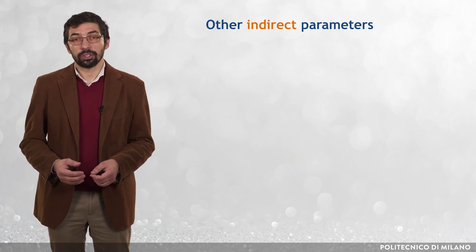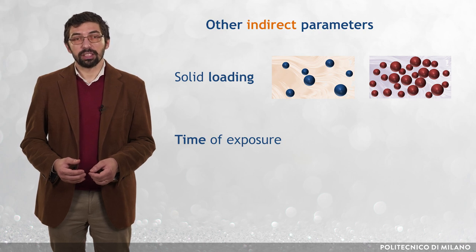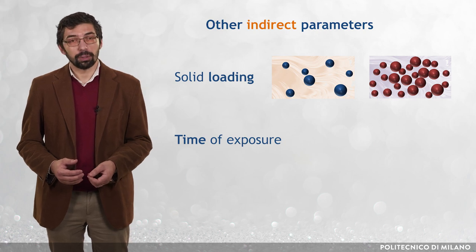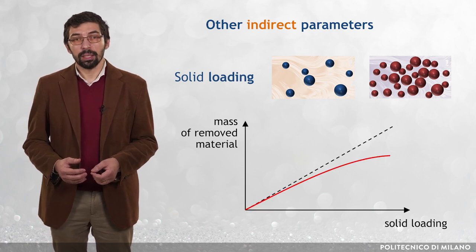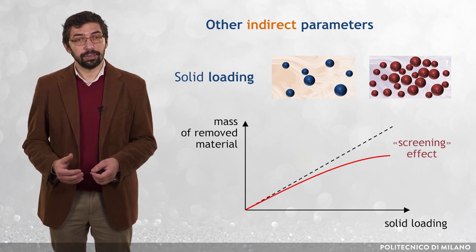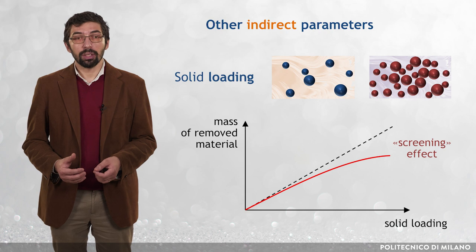Finally, two other parameters affect solid particle erosion: the solid loading, that is the amount of solid in the flow, and the time of exposure to wear. Note that the effect played by these variables is indirect, in the sense that it is not related with the erosion potential of a single particle, but with the development of the particle-laden flow. As far as solid loading is concerned, it has been observed that, for a given time of exposure, the mass of removed material increases less than linearly with the solid loading. The most recognized interpretation is based on the so-called screening effect occurring in dense flows: after impinging the target material, the rebounding particles collide against the incoming ones, reducing their erosive potential.